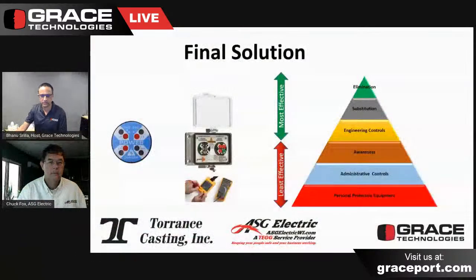Yeah, that's true. So as you mentioned, you chose to go with a grace voltage test station on your load side for absence of voltage verification, correct? What I'm showing on screen is the voltage indicator — the one with the blue faceplate — which is purely for alerting on voltage presence, so the qualified worker or task-qualified technician outside the cabinet knows there's voltage or hazardous energy present on the line side as well, correct?